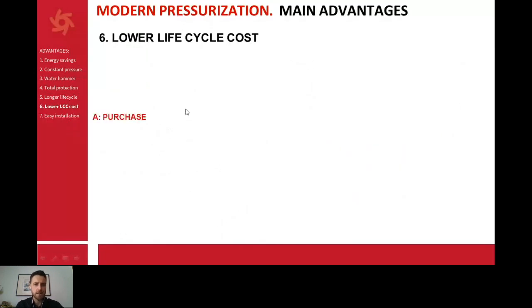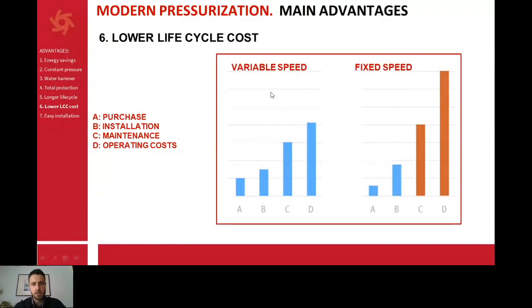What's this? As I said in the beginning, in the differences between old and new systems, there are four main aspects to take into account: the purchase, installation, maintenance, and operating costs over all the life of a booster set. What I want to say with this is that in a variable speed booster set, these are the costs from A to B to C to D. The purchase is the least important. As I said in the beginning, the important cost is the operating cost. This is the highest cost of the life cycle of the booster set. So in a variable speed set, this is the operating cost, and these are the operating costs in a fixed speed booster set, much higher. So it is very important to install a new modern pressurization booster set.